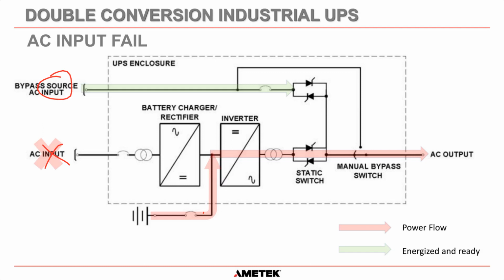And the reason behind it is, as a company, as a UPS manufacturer, we have no idea why this AC input has gone out. It may well be there has been a catastrophic event in that MCC and many other loads within the plant have been switched off, or many other pumps are starting or being turned off. So it could well be that the power in the plant is very, very unstable and the frequency is going all over the place and the voltage is going all over the place. So the bypass voltage could be very unstable.